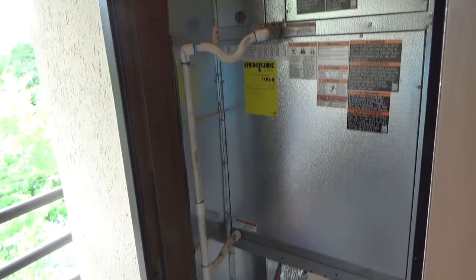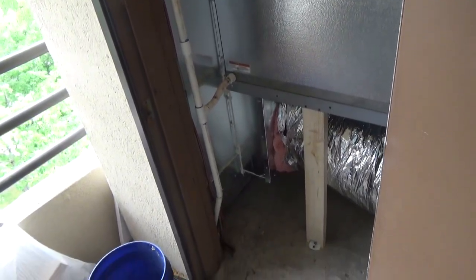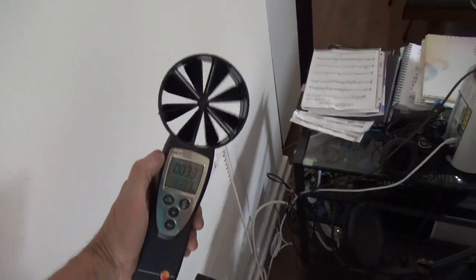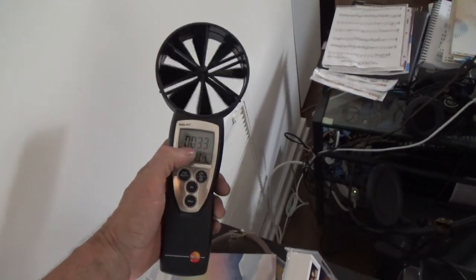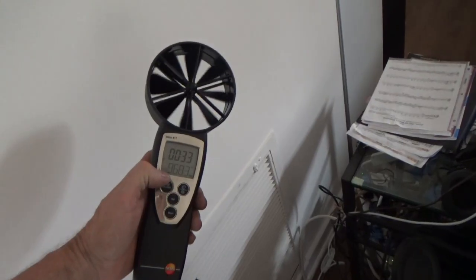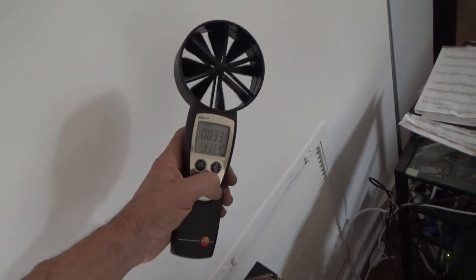Now the most important part of the job is checking the airflow. And that's on the return right here. And I use this meter. I put in the area, and 0.85 is the factor for these grills. And so my first check, I need 1,000 CFM, and I'm getting 968. So I'm gonna bump the fan up 1 speed and then measure again.